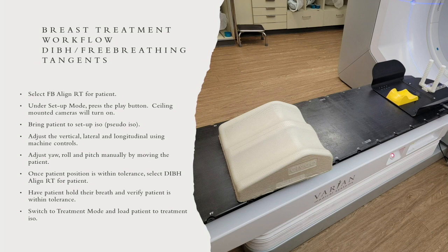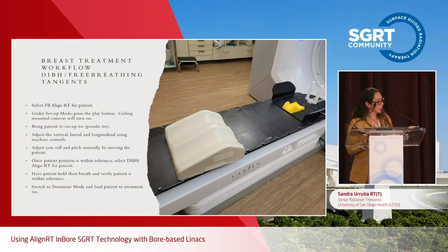Once the patient is in position and is within tolerance, you're going to pause the video feed, select the DIBH scan, and press play. You're going to instruct the patient to take a breath in and hold, and you'll see that the patient will move into tolerance for treatment. Once everything looks good, you're going to switch to treatment mode and load the patient for treatment.